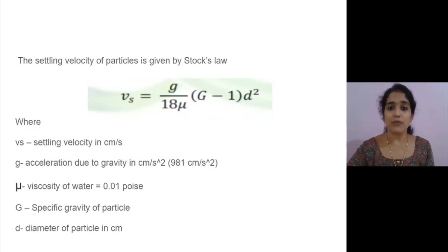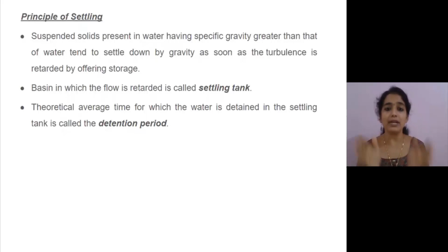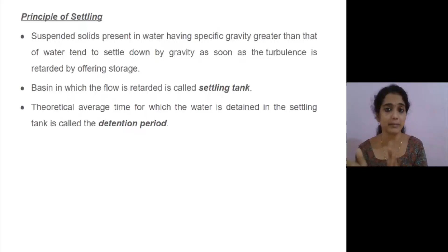Next, the principle of settling. The suspended solids present in water having specific gravity greater than that of water tend to settle down by gravity as soon as the turbulence is retarded by offering storage. This is the basic principle of settling. The basin in which the flow is retarded is called the settling tank, and the theoretical average time for which water is detained in the settling tank is called the detention period. It is very important in the design of settling tanks, sedimentation tanks, and all other water treatment processes.